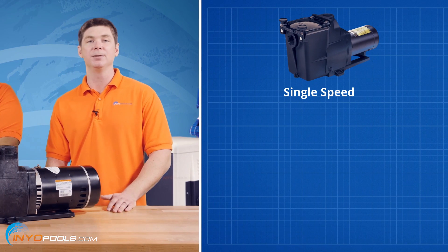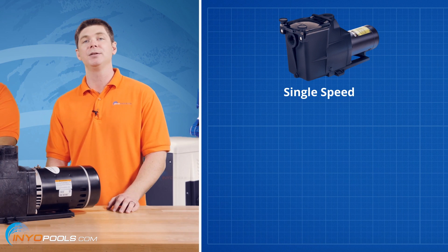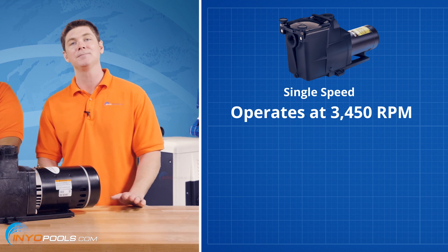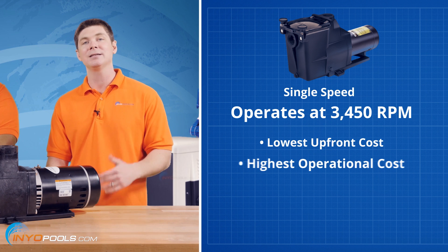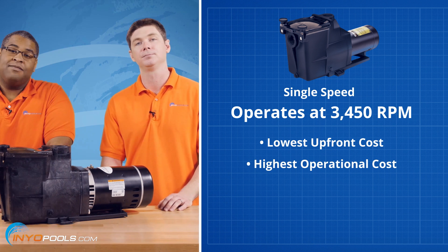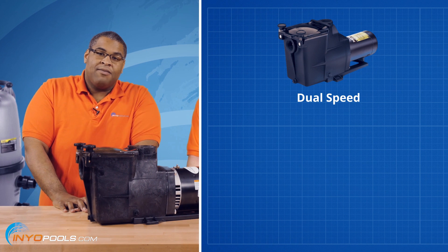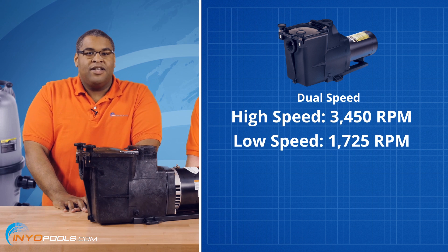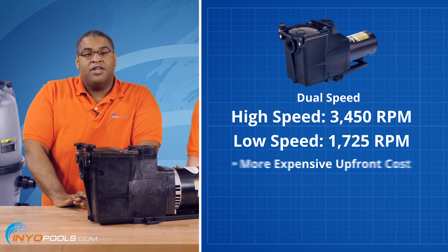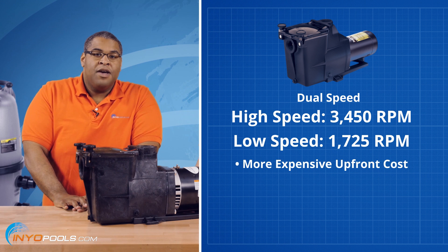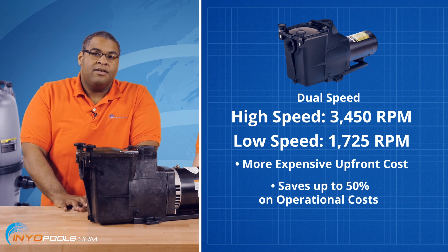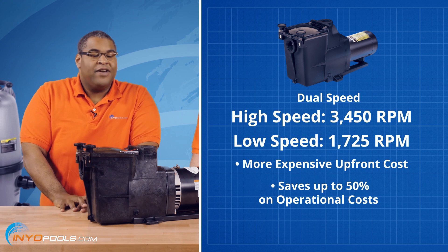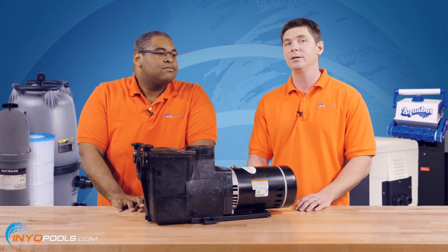The most common type is a single speed pump. It operates at a single speed of 3,450 RPM. This kind of pump has the lowest upfront cost but the highest operational cost. Next up is the dual speed pump. It operates at a high speed of 3,450 and a low speed of 1,725 RPM. It has a more expensive upfront cost compared to single speed, but can save you about 50% on the electric bill. Another benefit of running on low speed is that it's very quiet.